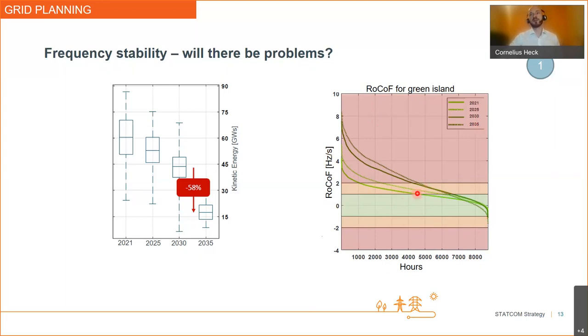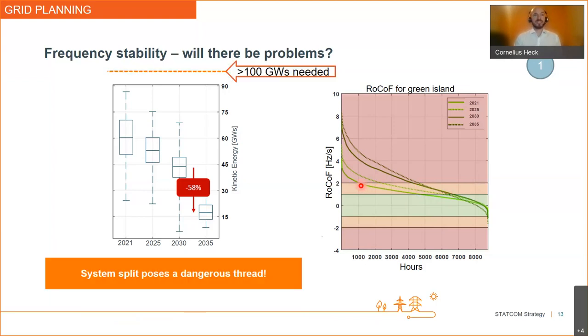And as you can see, already in 2021, for almost half of the year, we will be above the limit of 1 hertz per second. And looking at 15 years into the future, this threshold will be violated in almost 3/4 of the year. And even the 2 hertz per second limit will be violated 4 times as often as today. So the system split really does pose a dangerous threat.